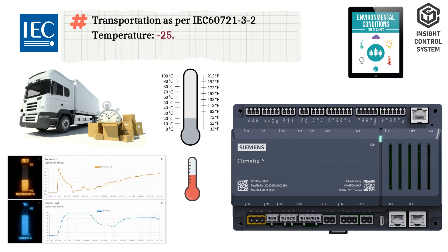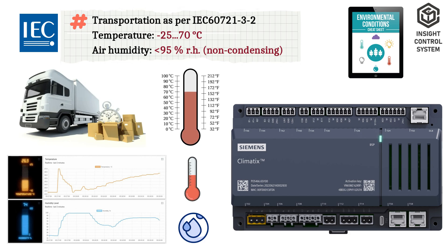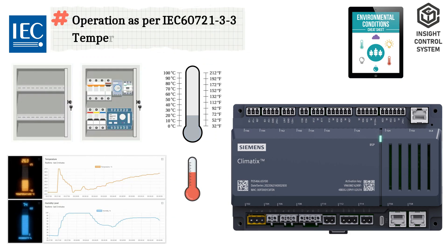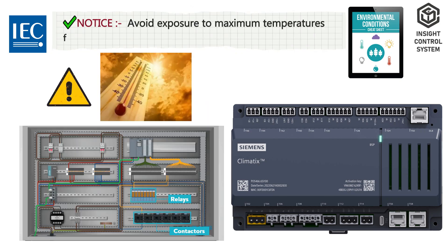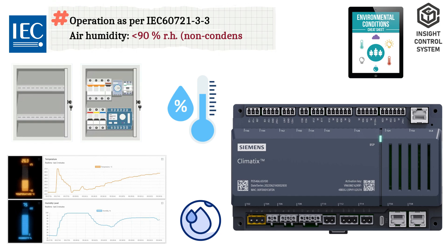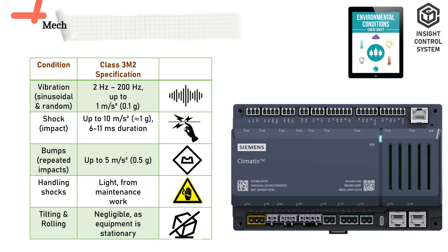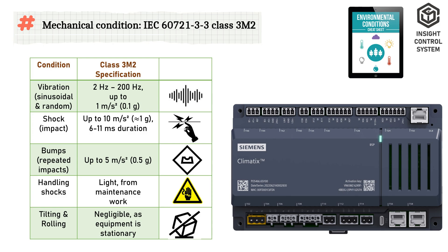In transportation: temperature minus 25 to 70 degrees Celsius, air humidity less than 95% RH non-condensing, mechanical condition class 2M2. In operation: temperature minus 20 to 60 degrees Celsius — note: avoid exposure to maximum temperatures for prolonged periods. Air humidity less than 90% RH non-condensing, mechanical condition class 3M2.